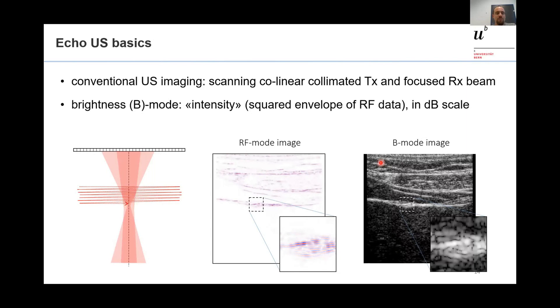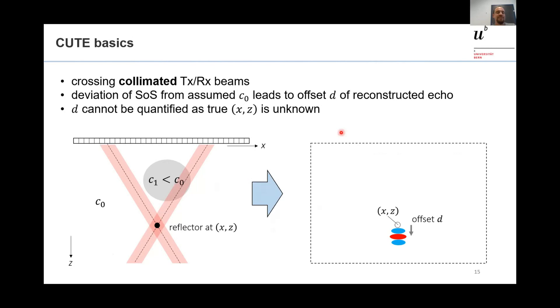In CUTE, we make more use of the flexibility of linear array transducers. We use collimated beams and explicitly steer them at a certain selection of transmit and receive angles. When two beams cross at a point containing a reflector, and there is a region inside the tissue with a different speed of sound than the background, the reconstructed position of the echo will differ from the actual reflector position. This offset is directly linked to the error in the assumed speed of sound C0.